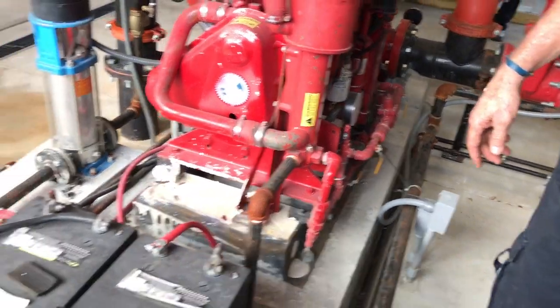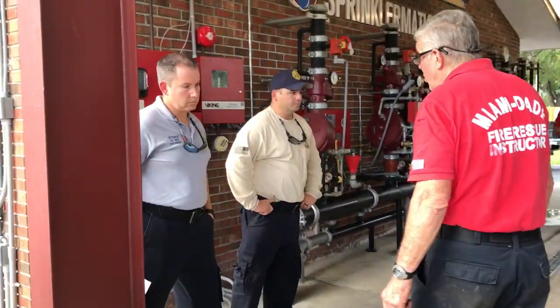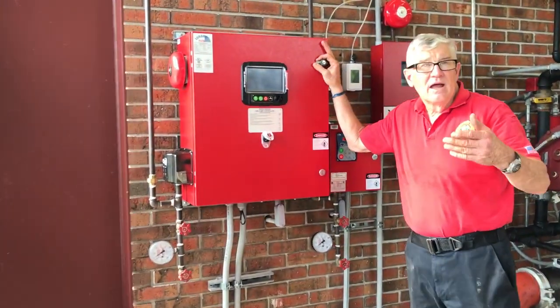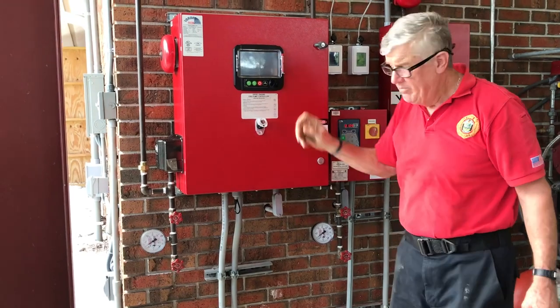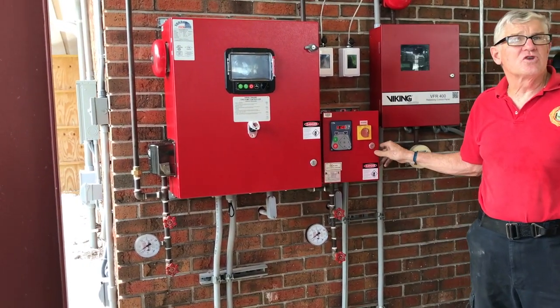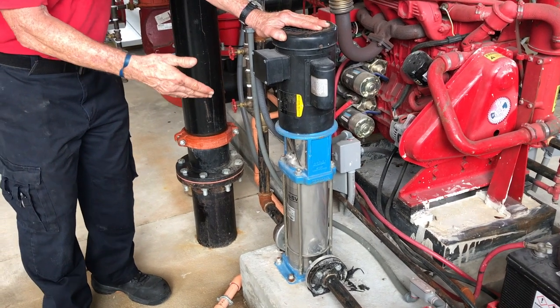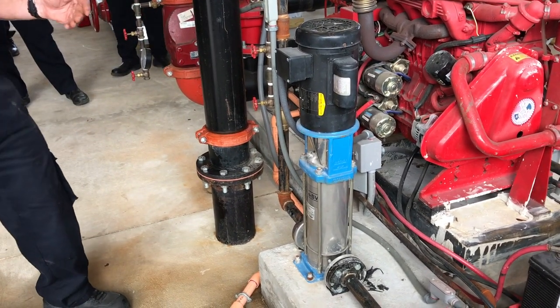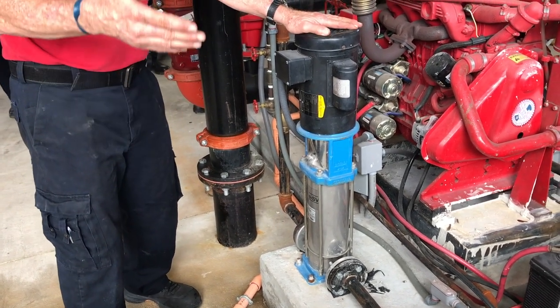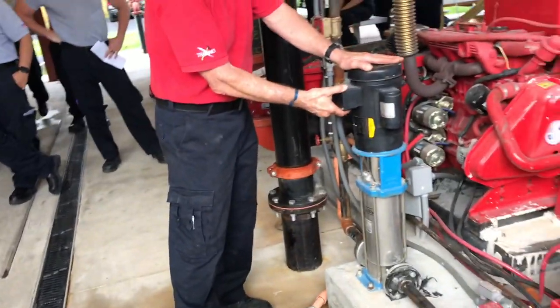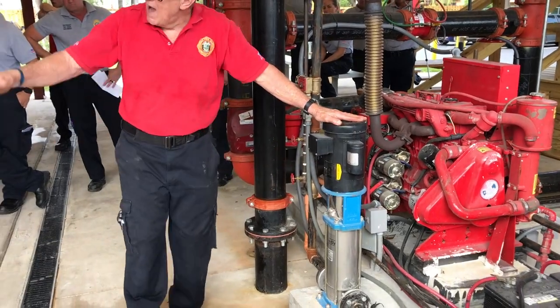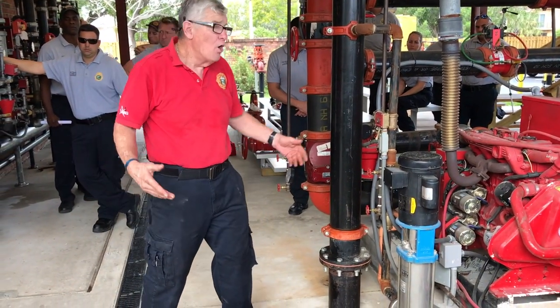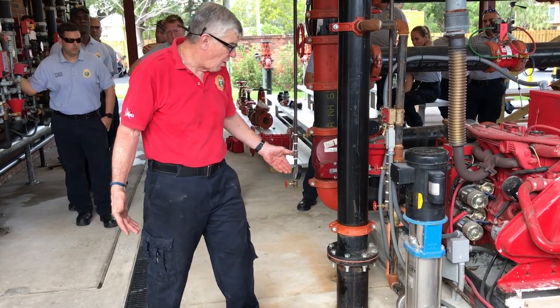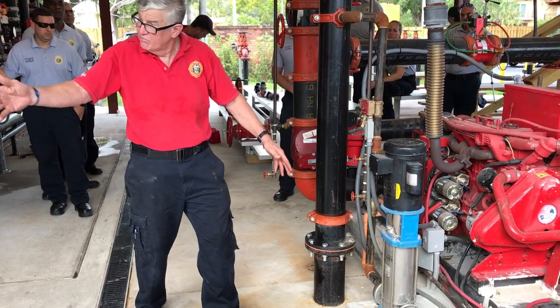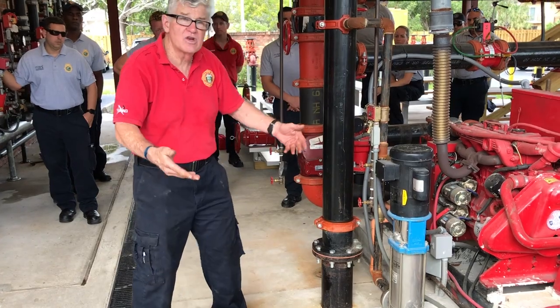Now, the brains of a fire pump is its controller. There's a water line that goes into the controller for the fire pump. There's a water line that goes on the controller for the jockey pump. Jockey pump is here. It's a low gallons per minute pump to compensate for minor fluctuations in pressure. When you have a significant flow of water, it overwhelms the jockey pump, which drops the pressure in the main pump controller to the point where the pump starts. So what we're going to do is run through a process here where we're going to drop our pressure. First, you'll hear the jockey pump run.